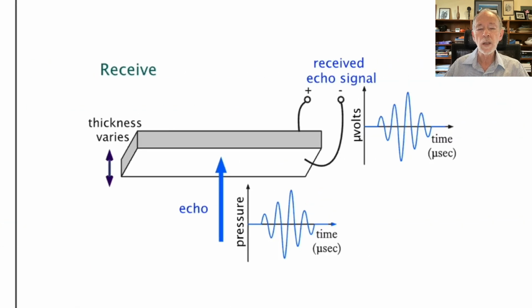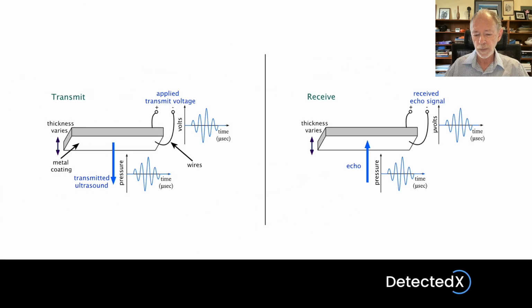On the right-hand side, we have a diagram showing what happens when the transducer is receiving ultrasound echoes. Those ultrasound echoes consist of pressure variations. So these pressure variations affect the transducer, setting it oscillating in thickness. Now they're very small amplitude, and therefore the thickness variations of the transducer are going to be very small. But nevertheless, this generates a voltage which is exactly equivalent to the ultrasound pulse. And so we get an electrical signal that exactly matches the received echo, and this can be received by the machine and processed to produce, eventually, an ultrasound image.